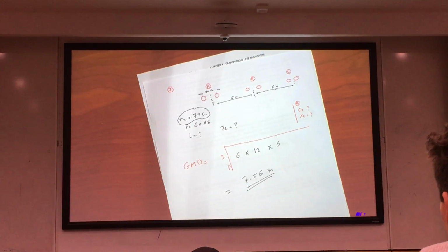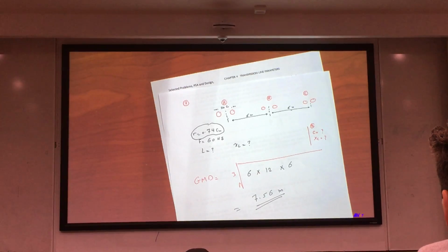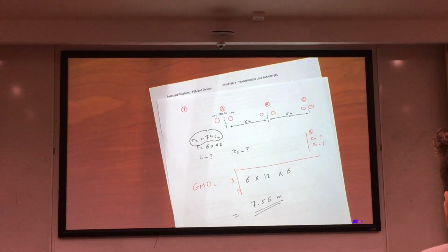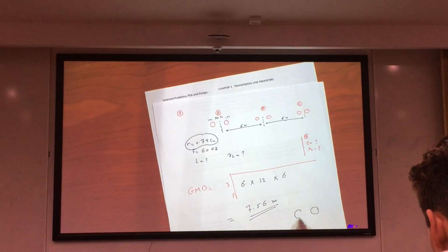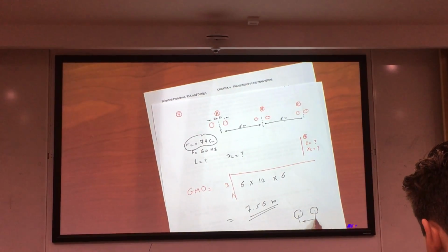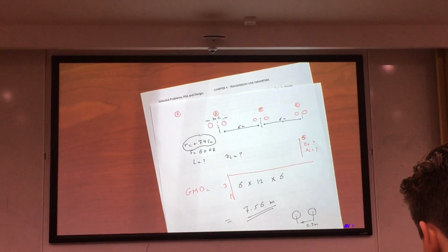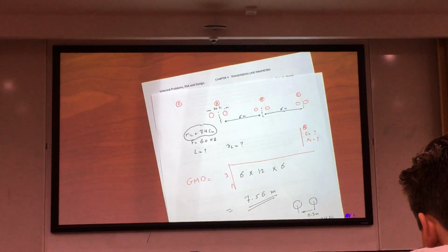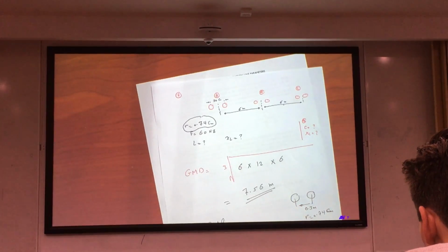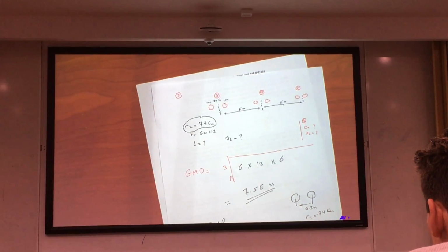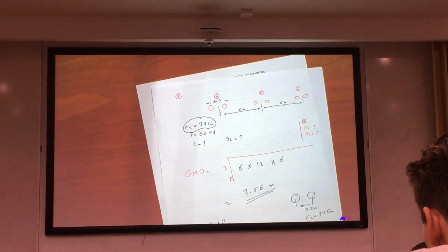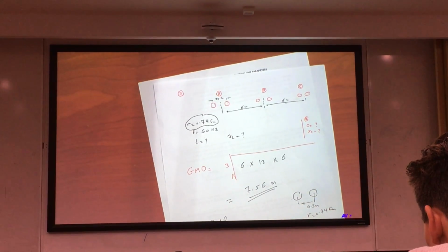What's given in the problem here is the radius for each conductor, and we have bundles. We have 2 conductors with each phase, so we have to calculate the geometrical mean radius for this configuration. 2 conductors spaced by a distance of 30 centimeters or 0.3 meter, and the radius is 0.74 centimeter. So the geometrical mean radius here for the L calculation is equal to, because there are 2 conductors, the square root. First conductor, I'll write r dash, which is 0.74.